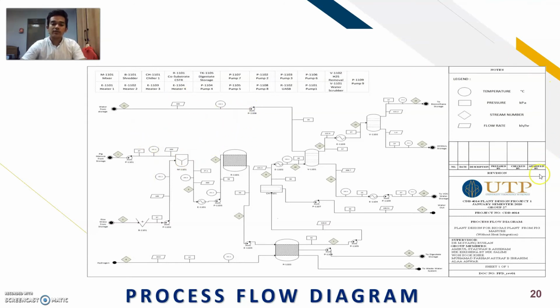For my part, I will explain the PFD, P&ID and also process instrumentation and control. So this is our PFD. We have included in each stream the flow rate, temperature and also the operating pressure. At the top right of the diagram, there is a legend which consists of 4 different shapes: circle, rectangle, diamond and parallelogram. The circle is for temperature, the rectangle is for pressure, the diamond is for stream number and the last one is for flow rate. At the top here is the equipment list and their equipment numbers.